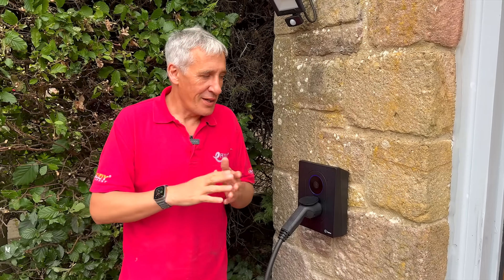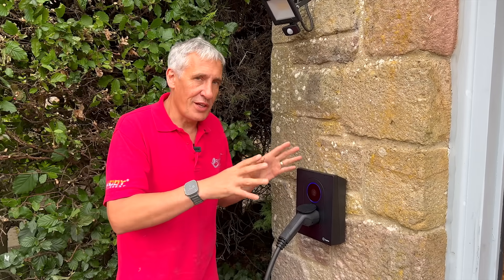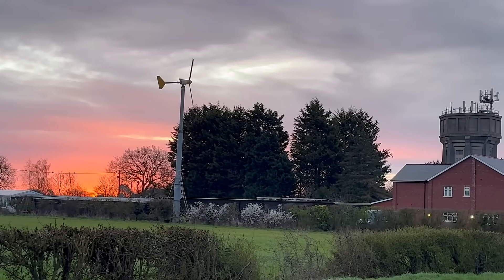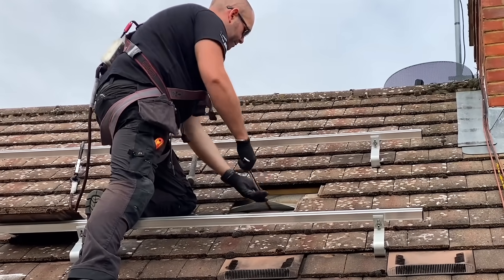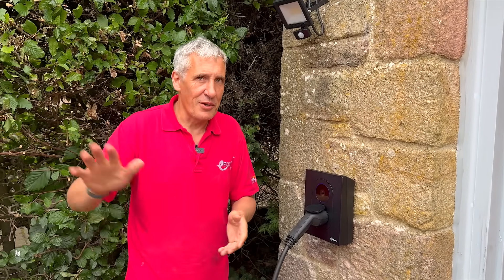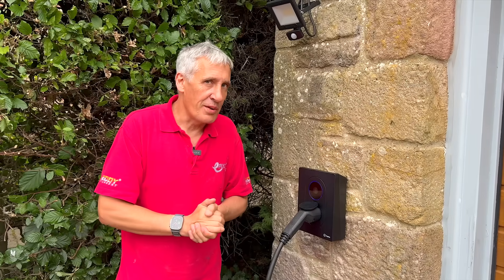Here's where things get a little grey: we call these EV chargers, but there's not much charging electronics in them, because the electronics that convert battery power back to AC are actually in the car. This creates approval challenges — how much power can you put back into the grid? Solar installers will be familiar with G98, which sets that limit at around 16 amps, but in the V2G world the approval sits with the car where the electronics are, and that car can move around or be replaced — that's essentially the last regulatory step we're waiting on.